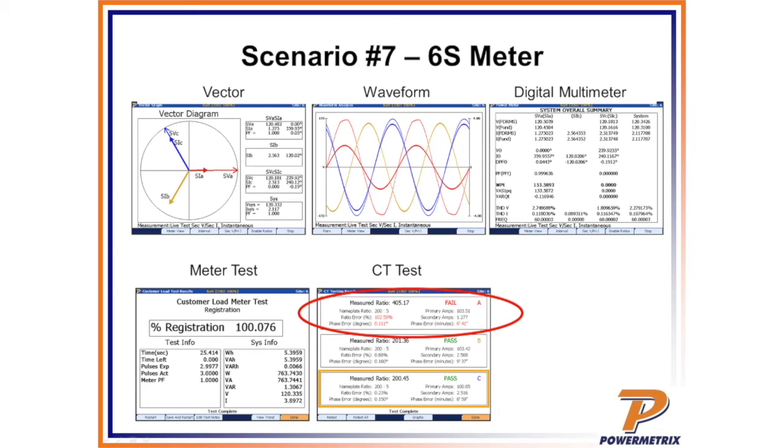Yeah, Lebo's made the suggestion that we could have incorrectly wrapped our flex 2 times. That could present a false error, but not true in this case. Ooh, Hammy, I think you may have got it. So Hammy says, without seeing the numbers, I would guess a wrong ratio CT. You got it, Hammy, good job.